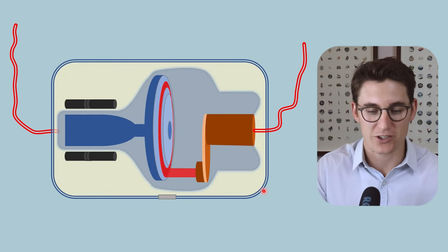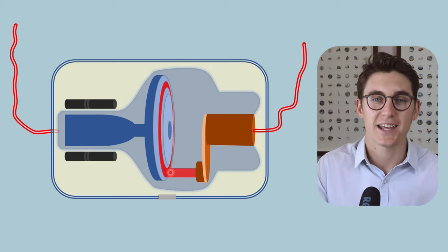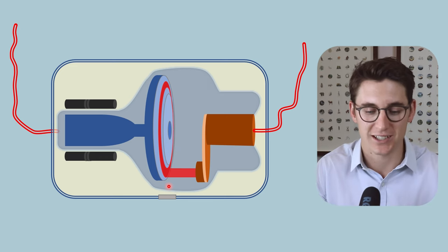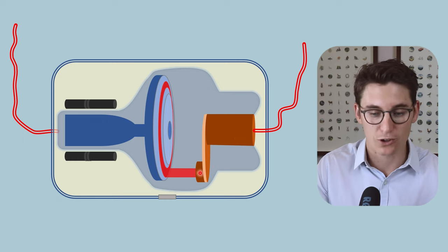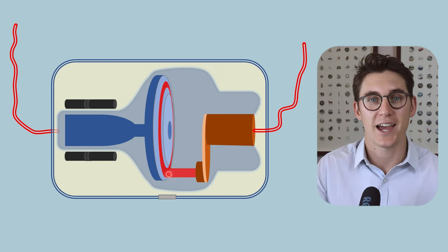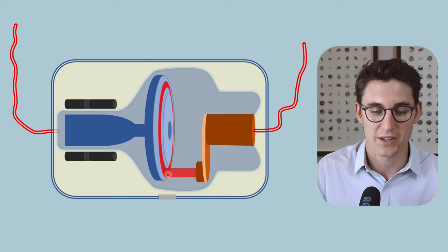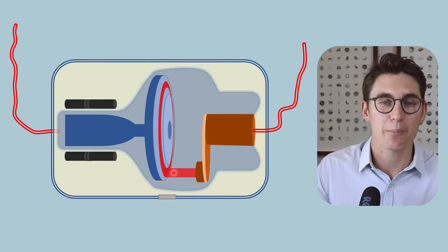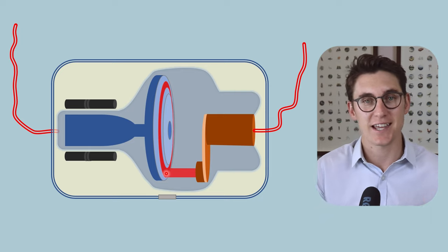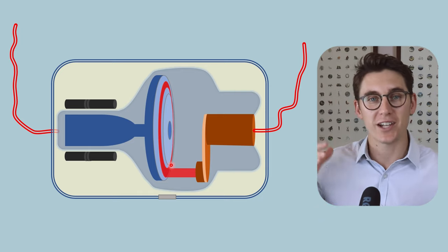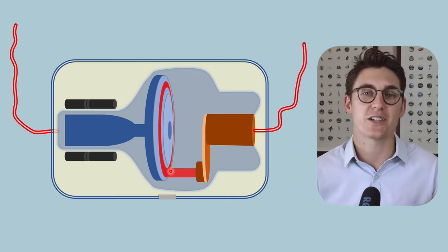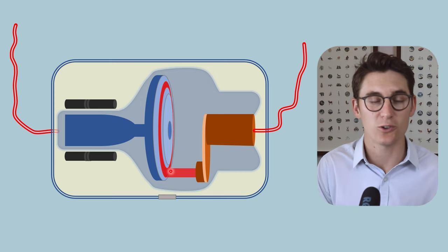So where exactly are these x-rays produced? Well, they're produced on the actual focal spot in the anode. They're not just produced on the anode surface — they are produced within the anode, like we've seen in our anode-heel effect talk. So you have our cathode producing electrons, our tube potential accelerating those electrons, those electrons striking our anode, and x-ray production occurring at this anode. Now a really common question is what happens to the energy of those electrons that strike the anode. Less than 1% of that energy is converted into x-rays, and the rest — over 99% — is converted into heat at the anode.